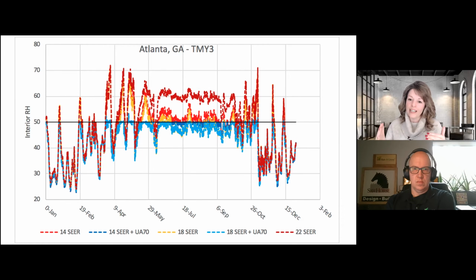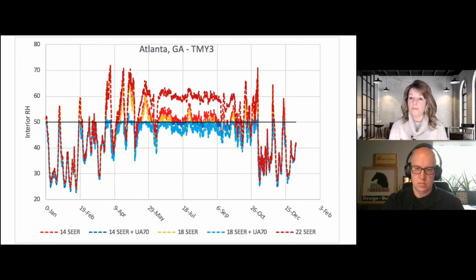What you're doing is slowing down the fan, creating colder coils, and delivering a smaller amount of cool air to the home, trying to remove more water. But there still has to be a load, a heat load, for that to work. So obviously you can see here, we're way out of whack in the shoulder seasons. And even here, it does such a good job of getting to that temperature and maintaining that temperature that it can't get the runtime it needs to actually get the water going down the drain. And again, this is BEopt, and NREL offers it on their website for free. The only caveat is it only works on a PC, it won't work on a Mac.